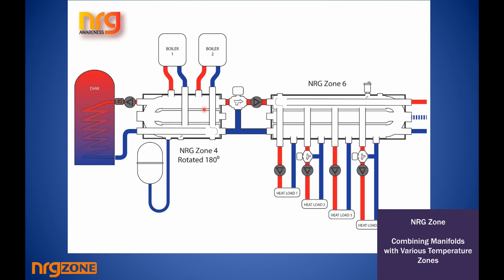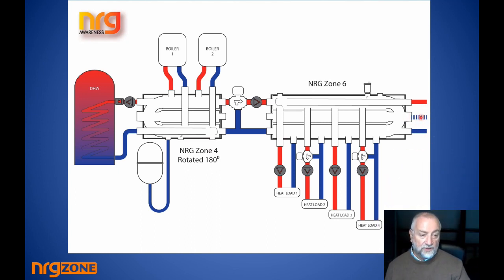Whereas you might decide to take a circuit from the right hand side and put that through a mixing valve, so you can have a controlled temperature leaving to the second manifold, and then you can divide that down further again with more mixing for, say, underfloor on zones B1, B2 and D1, D2, whereas you can have full temperature on zones A1, A2, C1, C2 and also on R1, R2, with even a return come back if you wished on the middle. It doesn't matter because all that water is going to be drawn down here in any case. So combining units is not an issue.